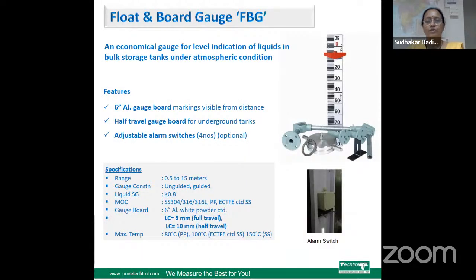The next one is the float and board gauge. This is an economical gauge which is used for large bulk storage tanks under atmospheric conditions to see the liquid level. It uses a 6-inch aluminum gauge board which has markings that are visible from a long distance also. For underground tanks, you will get the scale board in half scale. Then adjustable alarm switches are also available with this gauge for control action. The range of this gauge board is up to 15 meters.